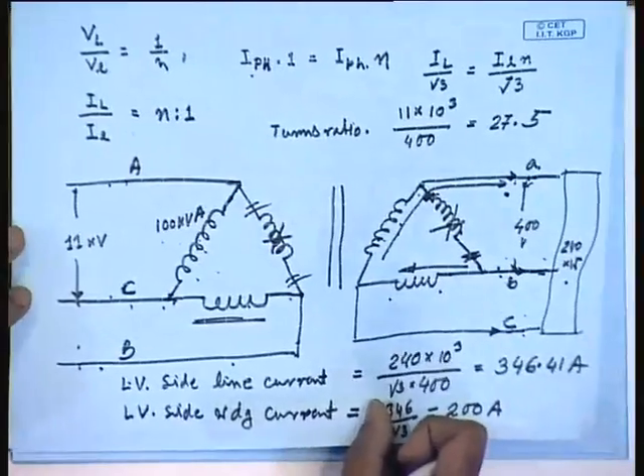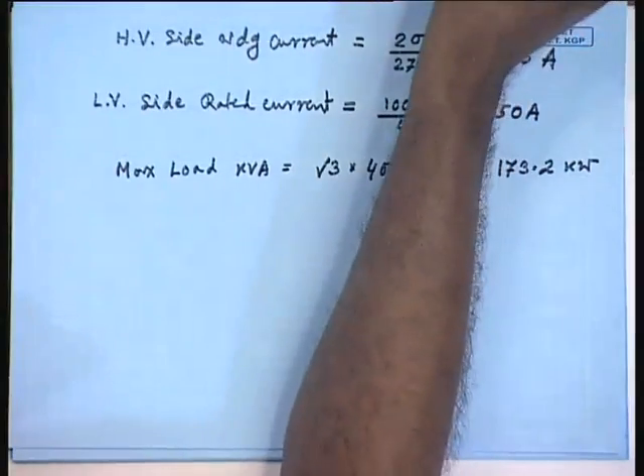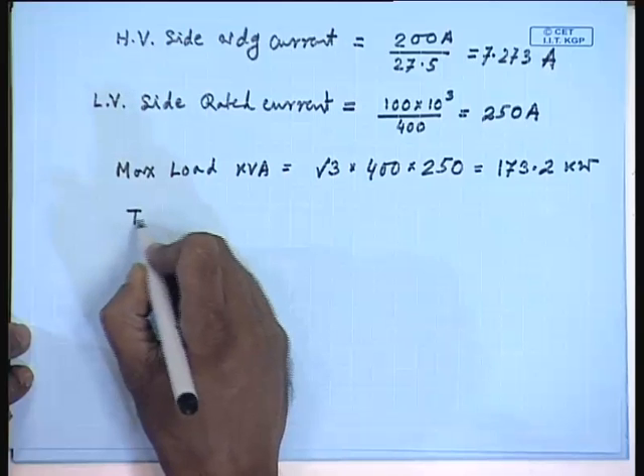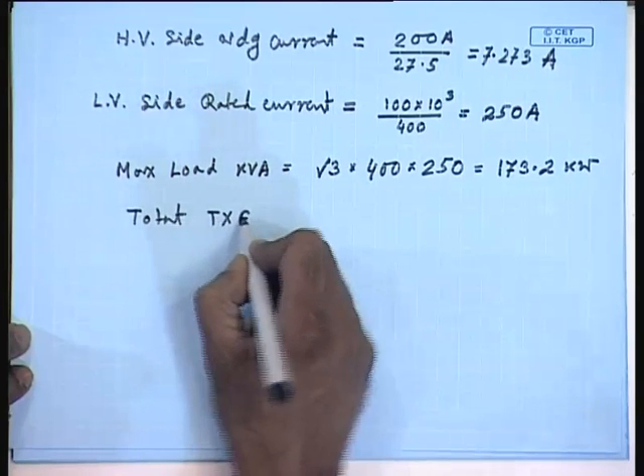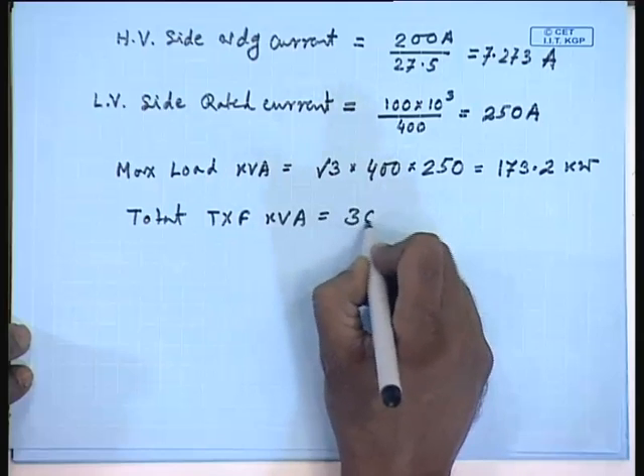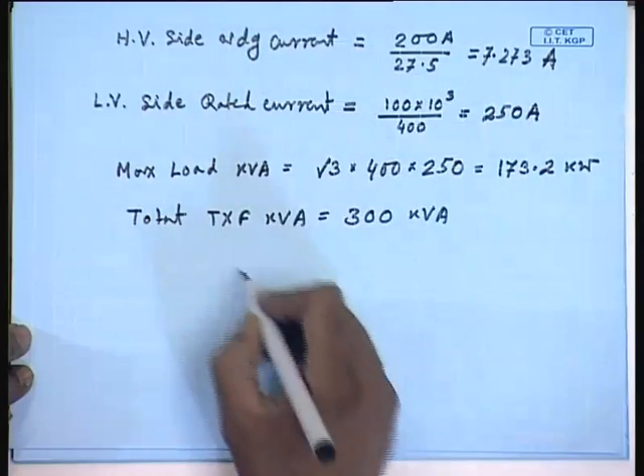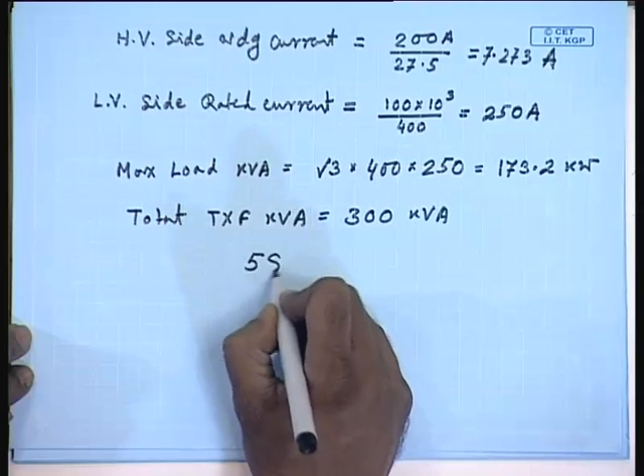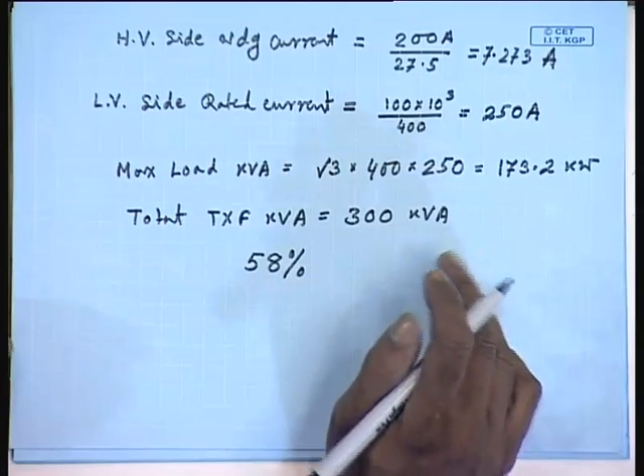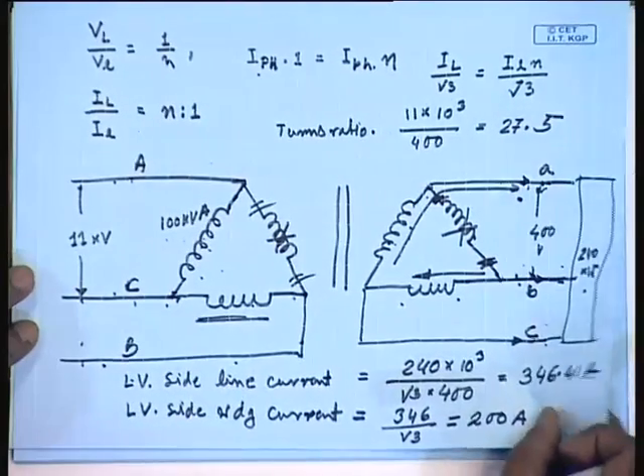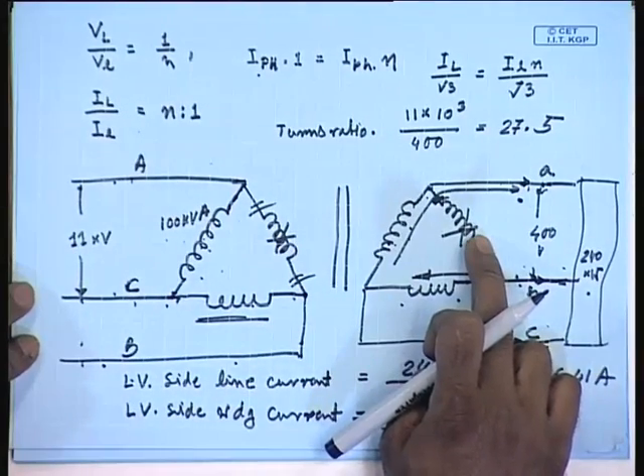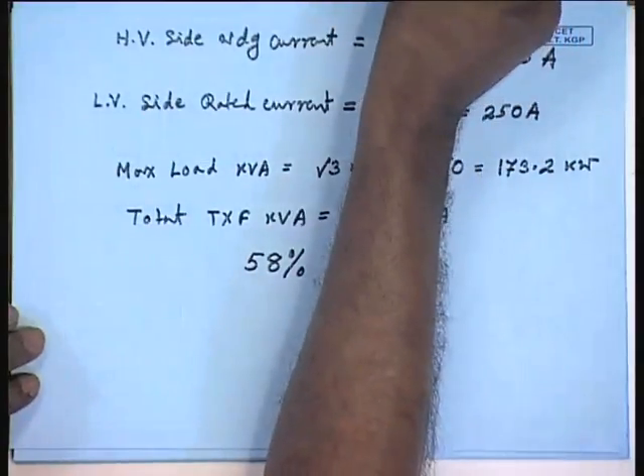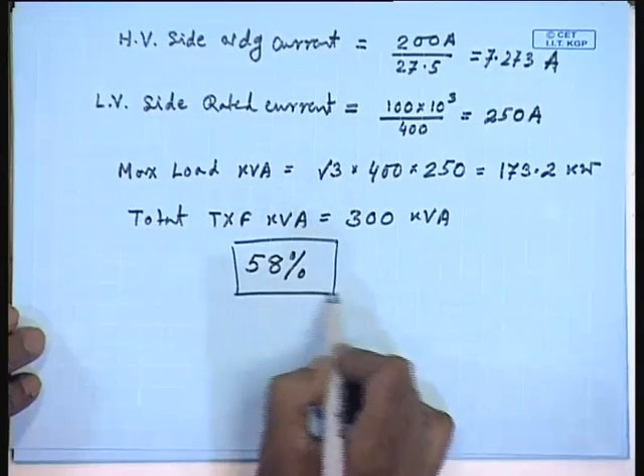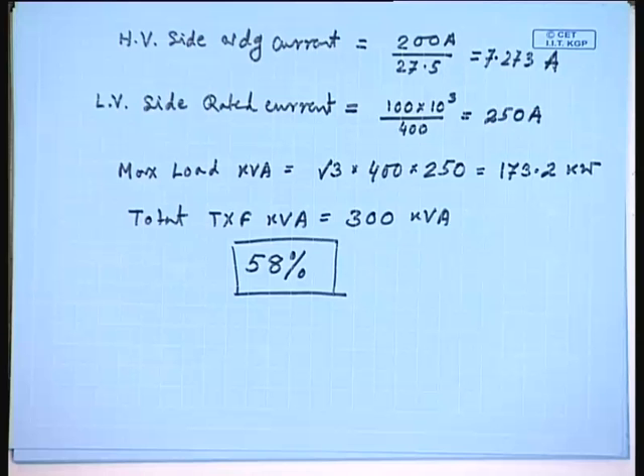Please note that the total rating of these transformers is 300 kVA. Hence, with open delta we can supply approximately 58% of the total transformer kVA. Please note that we have removed one transformer. So, it was expected that we should be able to supply about 2/3 or 67% of the total kVA, but that is not the case. We can supply only 58% of the total installed transformer kVA. Thank you.